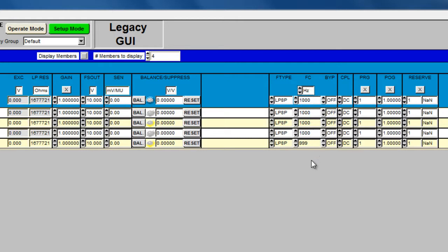The PFI signal conditioner offers a programmable filter characteristic known as the filter mode. The PFI filter mode settings offer a flat and pulse operating mode. This allows the filter transfer function to be set to perform in the manner of a Butterworth or Bessel type characteristic. These filter characteristics were developed by Precision Filters and allow the transfer function of the filter to be tailored to match the type of analysis being performed.